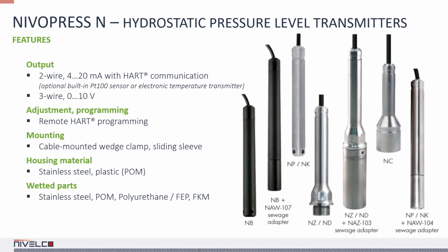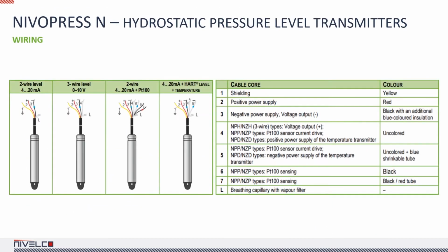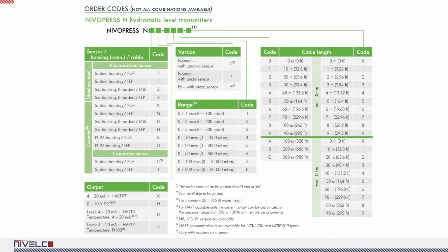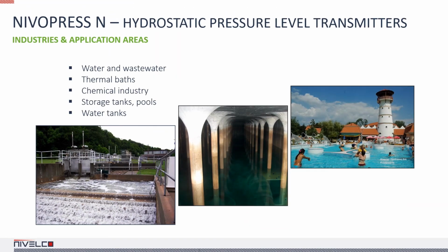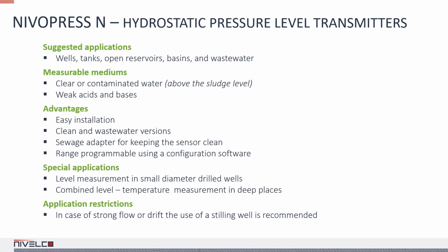The device is also available with a plastic cover. The version with a threaded process connection was primarily designed for a threaded sewage adapter. A temperature transmitter and a PT100 temperature sensor can be optionally integrated into the probe housing. The measuring range of HART-compatible devices can be adjusted between 2 and 130%. A wide range of accessories is available for NIVOPRESS transmitters. They are most common in water and wastewater treatment, for example wells and baths, but they can also be found in the chemical industry. They can also be used in small diameter drilled wells. If there's a strong current in the medium, using a stilling well is recommended.